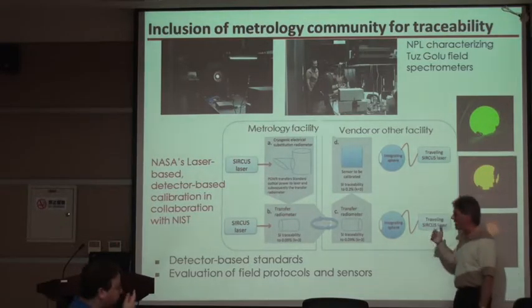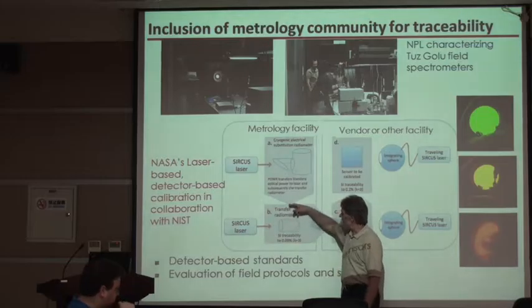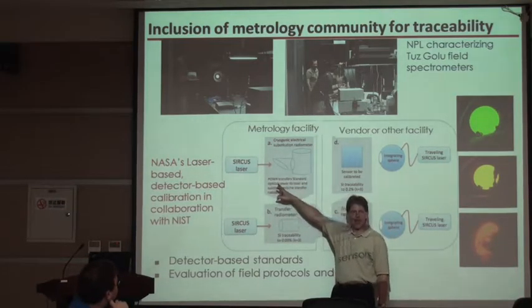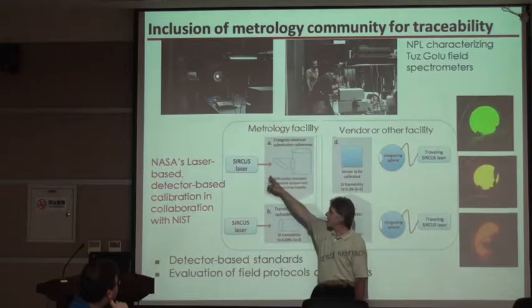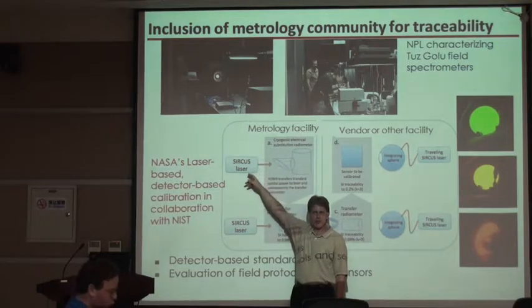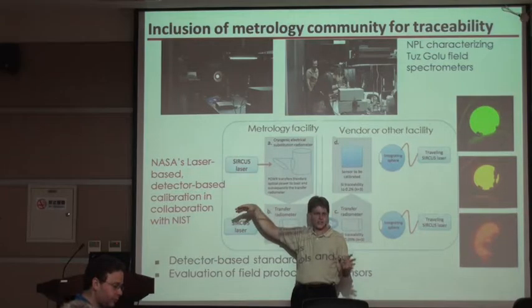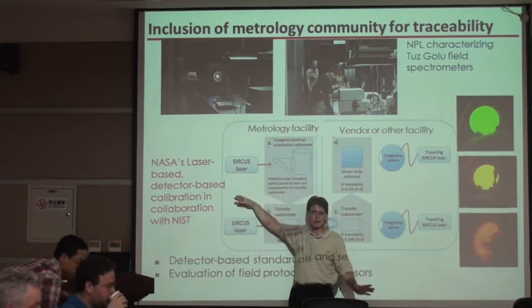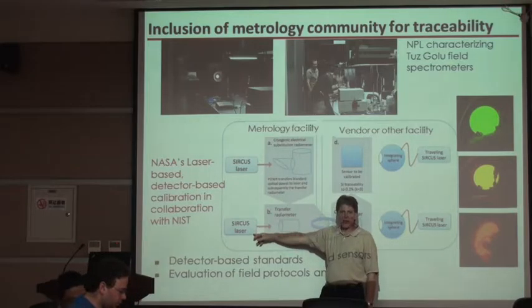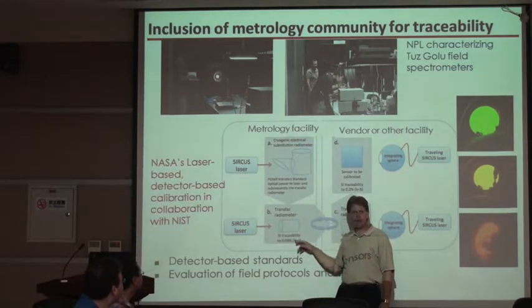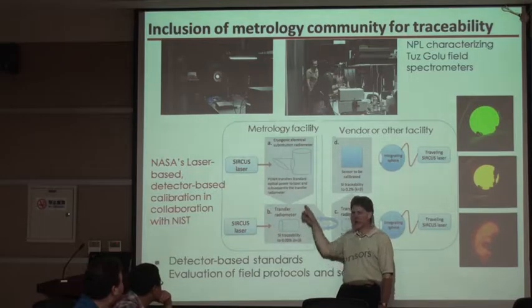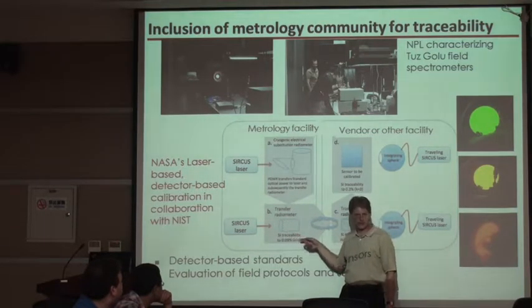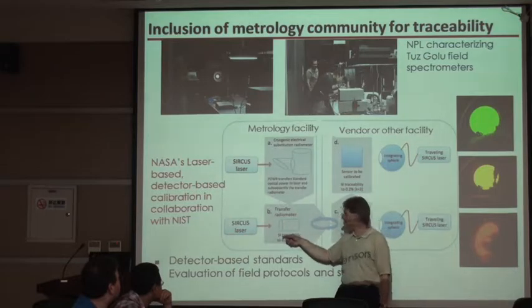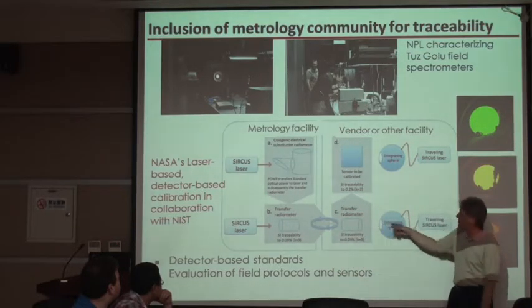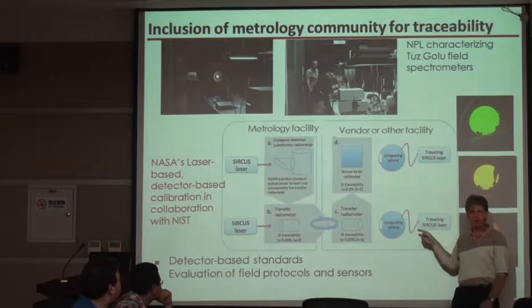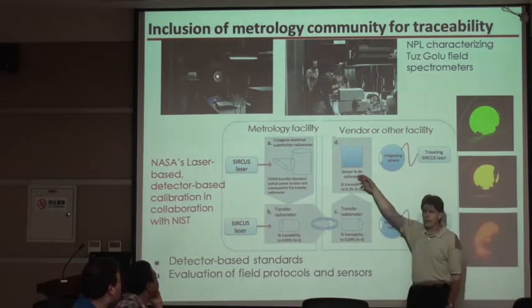What you do is build radiometers that are really well calibrated. We can go to a national lab, and they have a cryogenic radiometer that will look at a laser and measure the output of that laser perfectly, with something like 0.03% absolute uncertainty. You move that laser a little bit and have your radiometer look at it. This radiometer is much more stable than a lamp, so it will maintain its calibration and can go into another facility and calibrate a source. Then that source can be used to calibrate a radiometer.